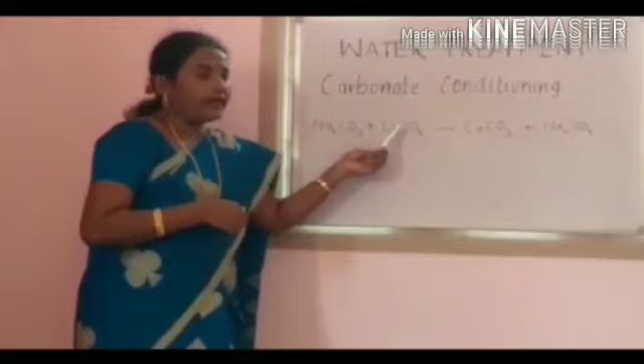This carbonate conditioning method is applicable only in low pressure boilers, not in high pressure boilers. In high pressure boilers, the sodium carbonate undergoes hydrolysis and gives sodium hydroxide. Sodium hydroxide causes caustic embrittlement. So the carbonate conditioning method is not applicable to high pressure boilers.